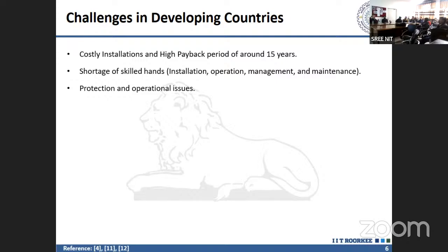But as you introduce renewables at different ends of your distribution system, now they are injecting power. Although this power is mainly given to the local load, once we say it can also supply the grid, this means they are giving a bidirectional component to the current. Now the current can flow in any direction. So because of this, these issues are appearing in the system.